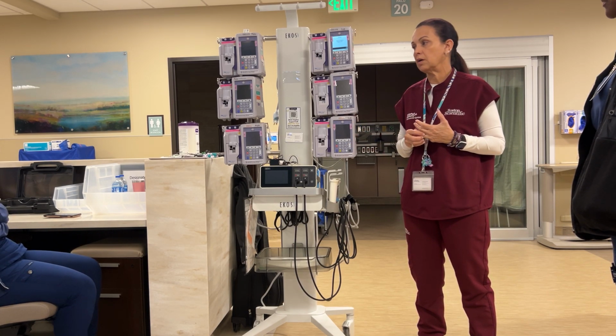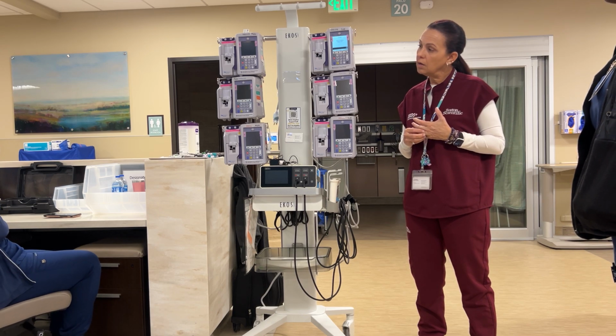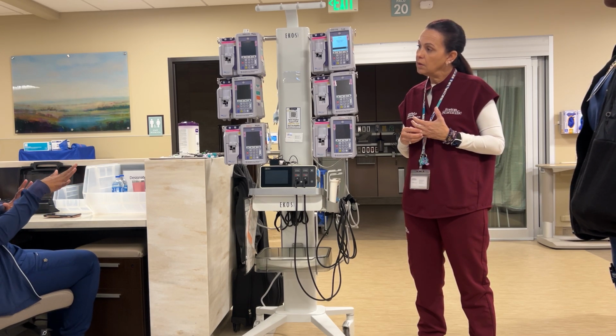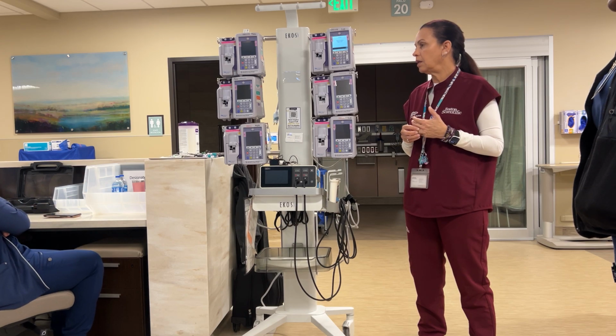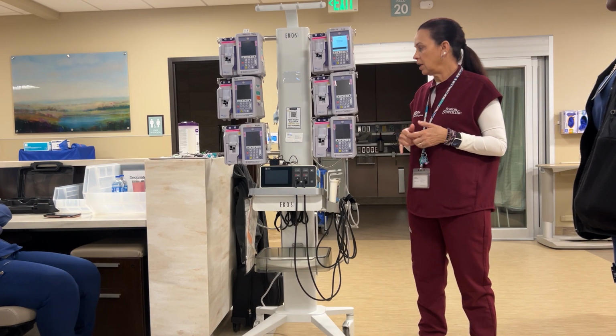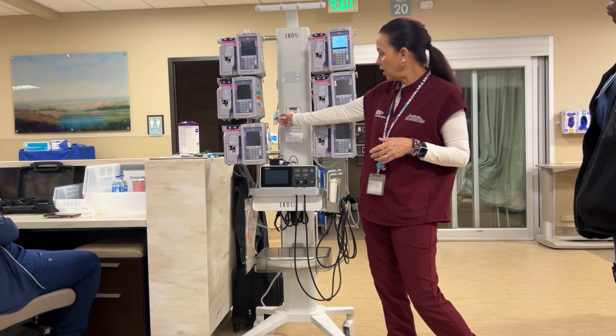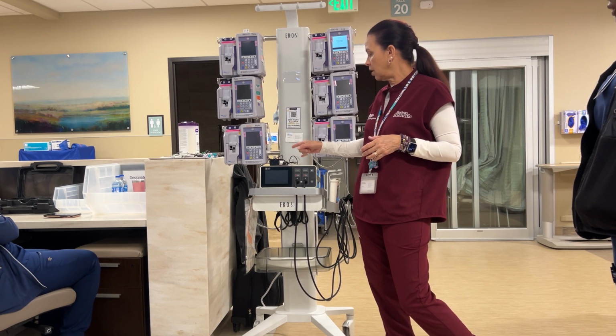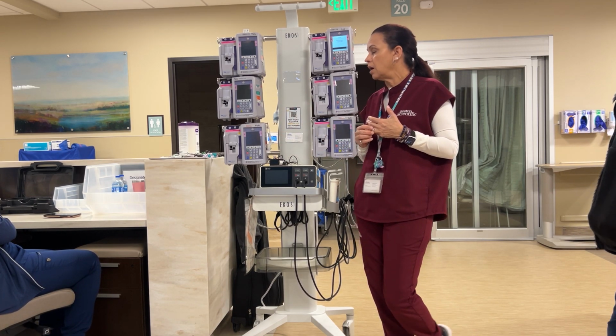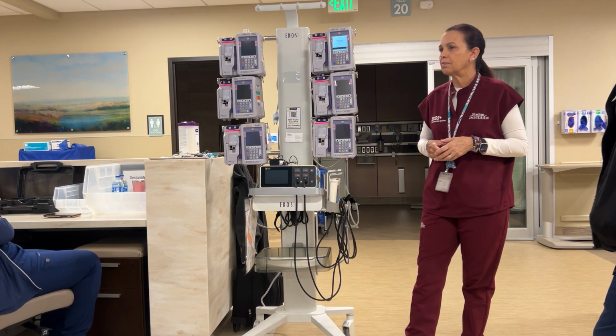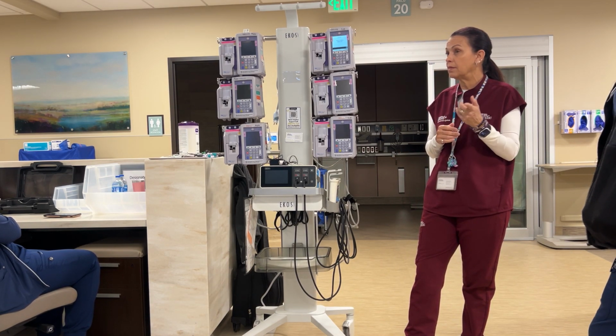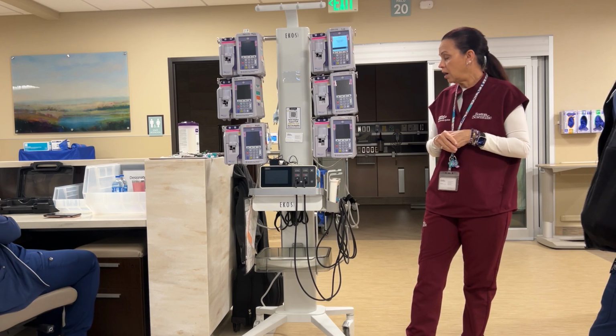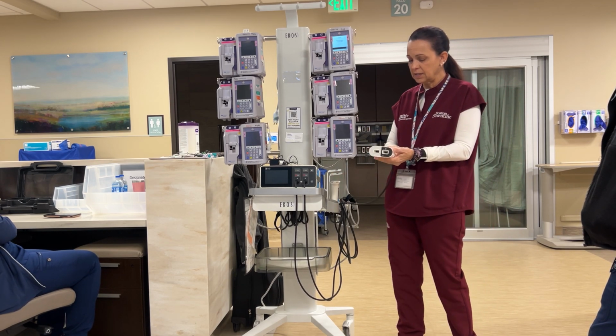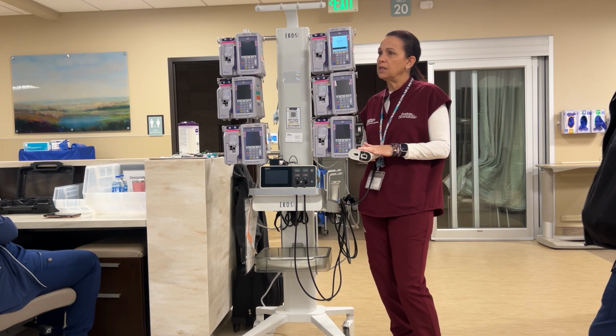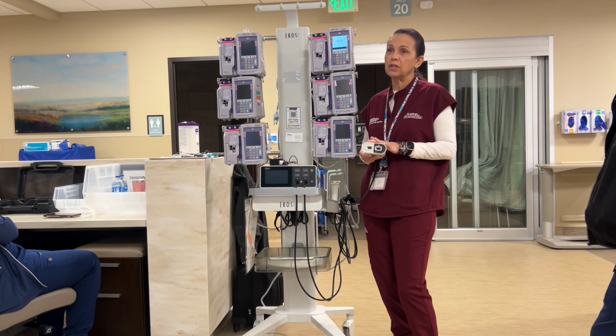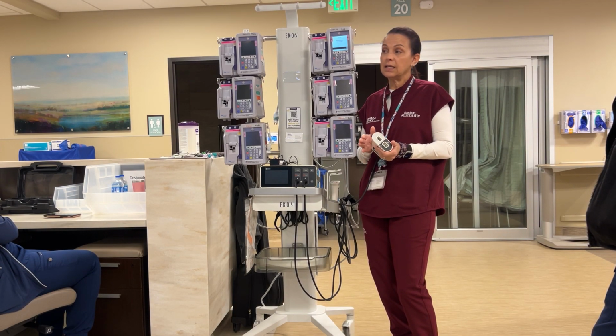You said something about the coolant, and if the system overheats, that alarm will go off. What do we do about that? You just call us. Yeah, that's gonna be a call to us, and you've got the helpline number, but my number is here also on the machine and on the control unit. Just call me, or you can call the cath lab and they'll call me, one of the two. Also, the CIC normally is gonna be down towards the end of the bed, but you wanna make sure it's not covered with a blanket or a pillow, because it can get warm.